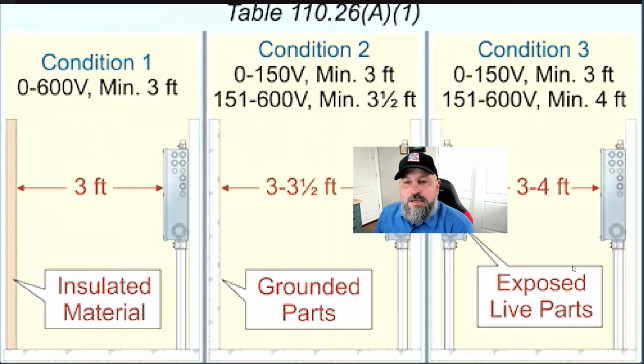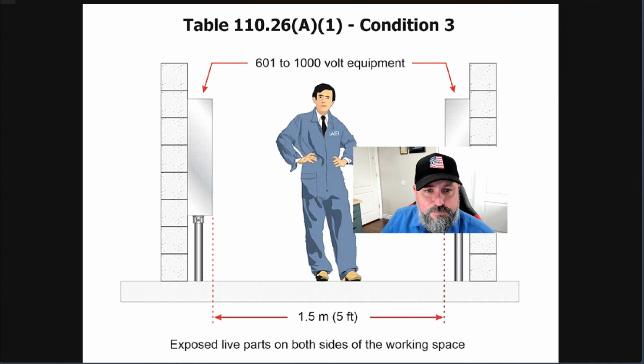Condition 3, and then here's where we fall into this, is that you've got a panel on this side and a panel on this side. So condition 1, it's still 3 feet. Condition 2, 0 to 150 volt, minimum 3 feet. 151 to 600 volt, minimum 4 feet, right? So you got to have 4 feet between these two covers here. And I have some other pictures here we can show. 600 to 1000 volt, 5 feet. So that's going to be your bigger equipment, right? Can't be across from there.